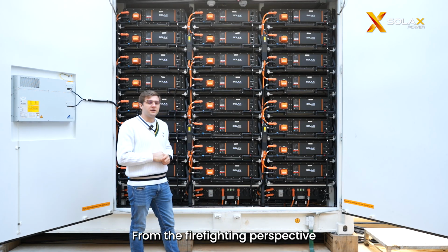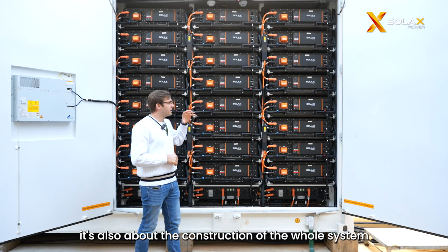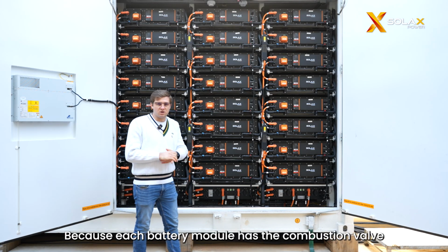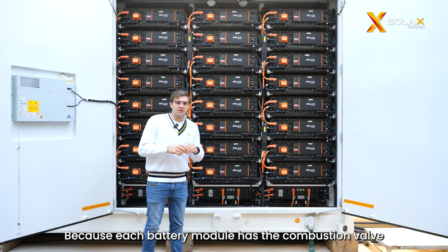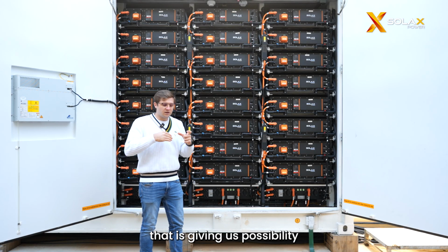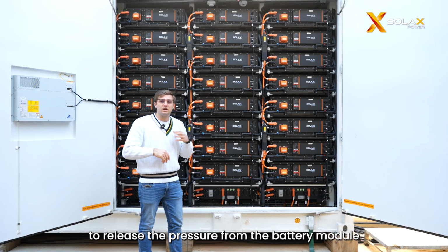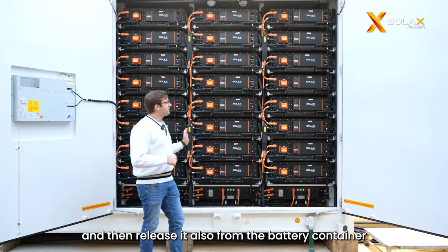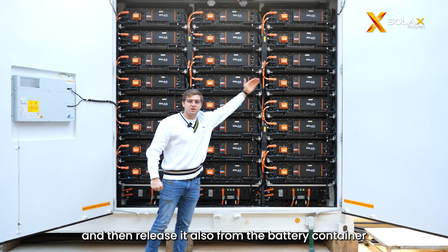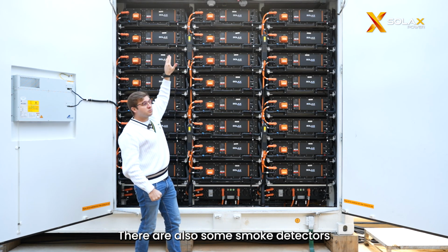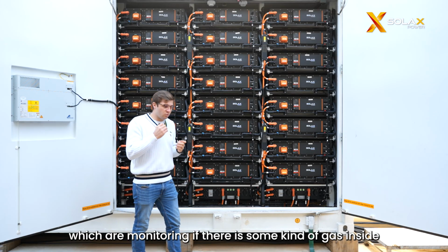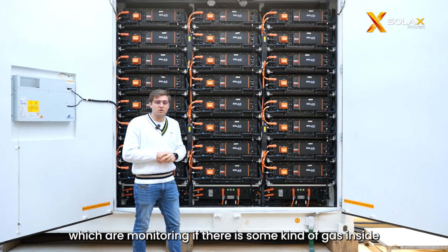From the firefighting perspective, it's also about the construction of the whole system, because each battery module has a combustion valve that gives us the possibility to release the pressure from the battery module and then release it also from the battery container. There are also smoke detectors which are watching if there is some kind of gas inside.